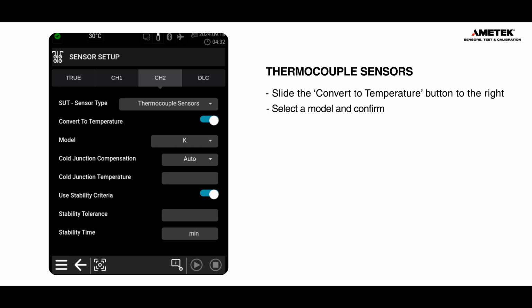Models. In thermocouple sensors, the models are K, N, R, S, T, U, B, E and J. Cold junction compensation. In auto mode, the calibrator measures the connector temperature for cold junction compensation. In manual mode, you can set a fixed temperature when an external reference is available. Cold junction temperature. When manual cold junction compensation is selected, you can set the temperature using the numeric keys.